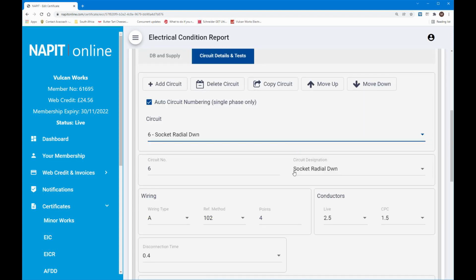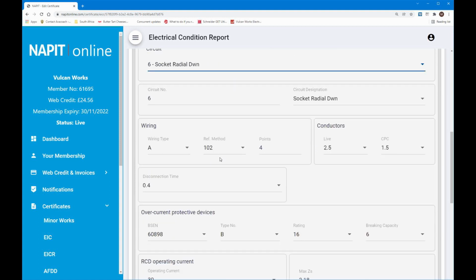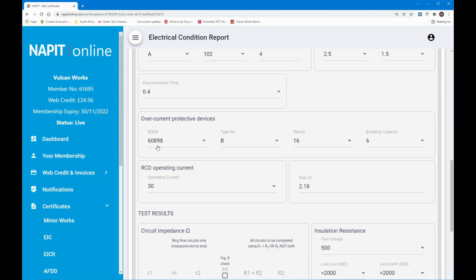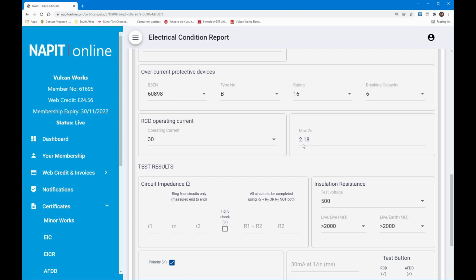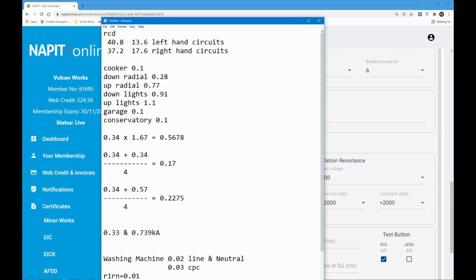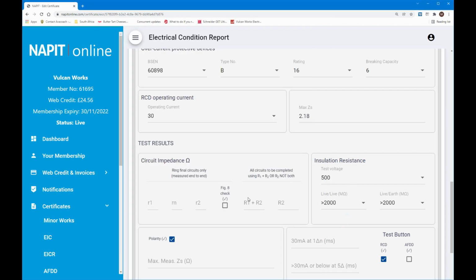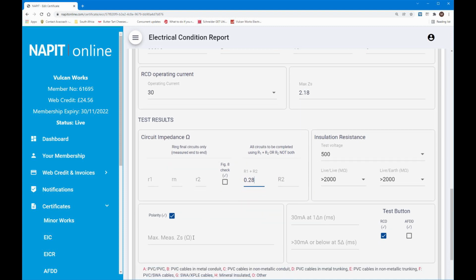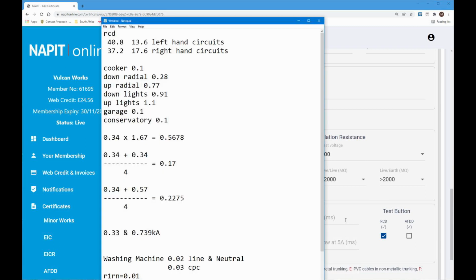So move on to the sockets on the downstairs radial. Okay, this is twin and earth, back to 102 for the reference method. There are only 4 points on this particular circuit. Again, we're down to 2.5, 1.5 on the twin and earth. Disconnection time 0.4, 60898 on that. And this radial circuit again is a 16 amp. Gives me a ZS maximum 2.18. The downstairs socket radial is going to be reading 0.28. Now I was able to do the insulation resistance test without a problem, and that, with the 0.33, gave me a reading of 0.61. And just to do the RCDs, again, like I said, it's 40.8 and 13.6.